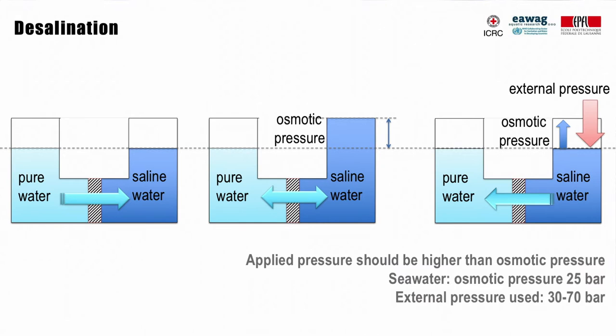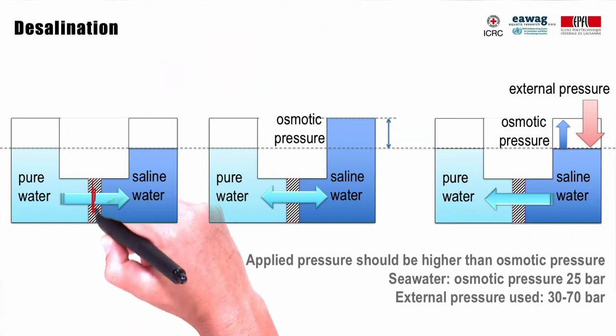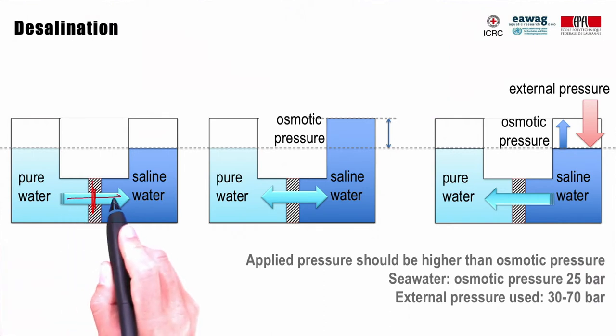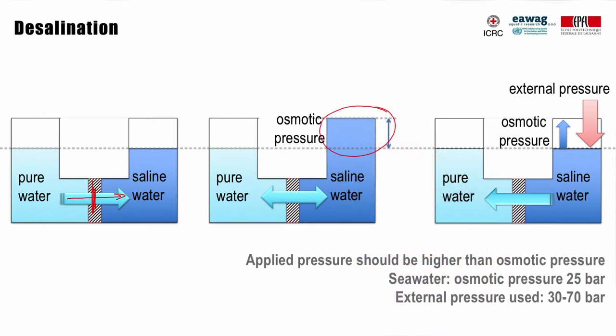Desalination is used to remove salt from sea or brackish water. If a semipermeable membrane is installed between pure and saline water containers, pure water will be drawn toward the saline water, creating an osmotic pressure. In order to overcome this osmotic pressure, external pressure higher than osmotic pressure needs to be applied. Seawater has an osmotic pressure of about 25 bar, which is why reverse osmosis systems are operated at 30 to 70 bar to achieve movement of pure water through the membrane. High-pressure pumps and good power supply are required, as well as pretreatment to protect membranes from fouling.